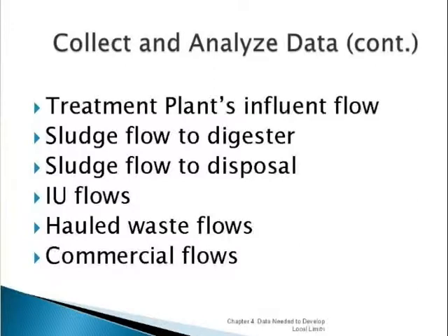And then, they obviously have data from their industrial users. They have sludge data that's required by their NPDES permit. So I would look over those and make sure they're adequate. If you know that their NPDES plant recently had an upgrade within the last 6 months, but they're submitting influent and effluent data from prior to that, you know that their removal efficiencies are probably not appropriate.